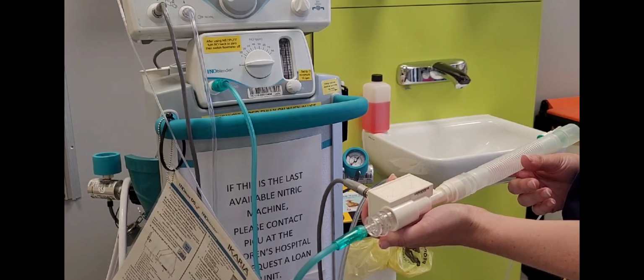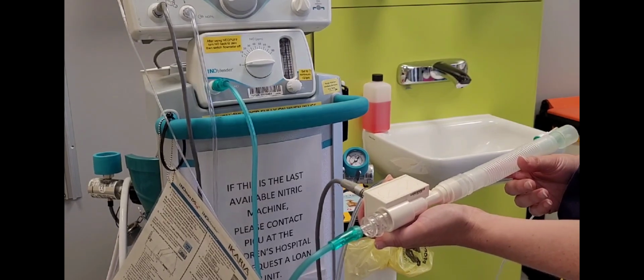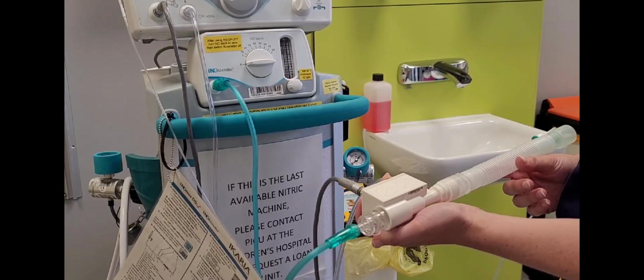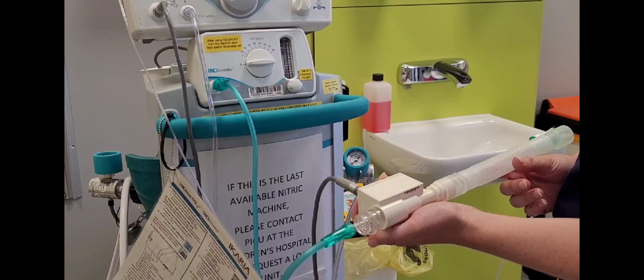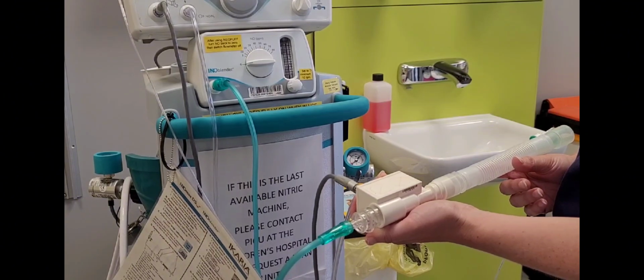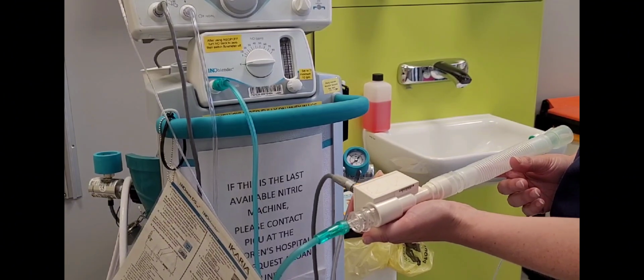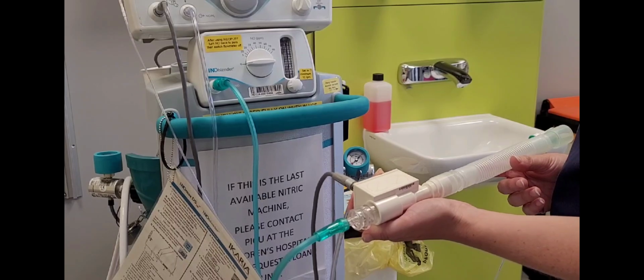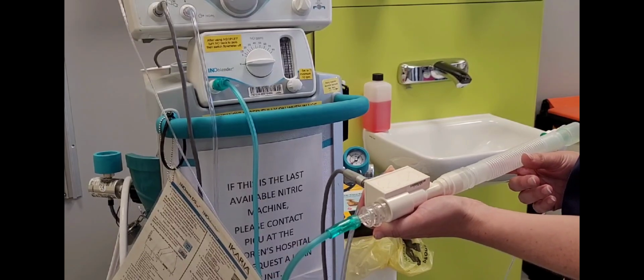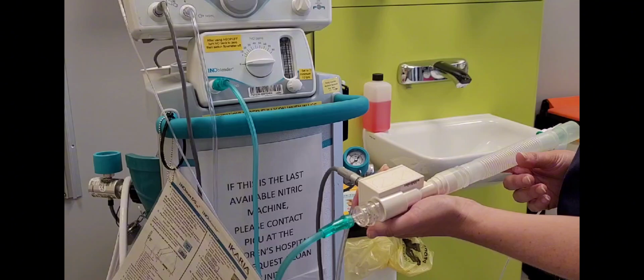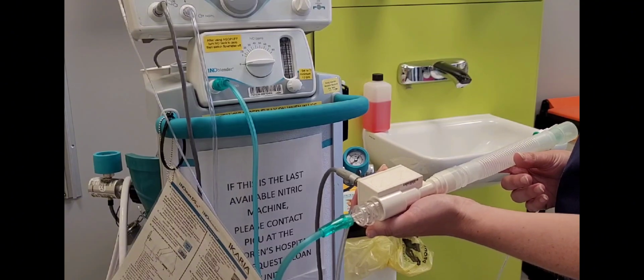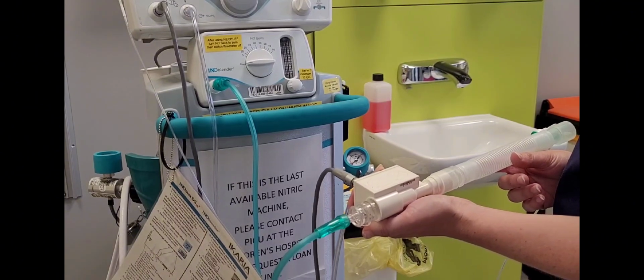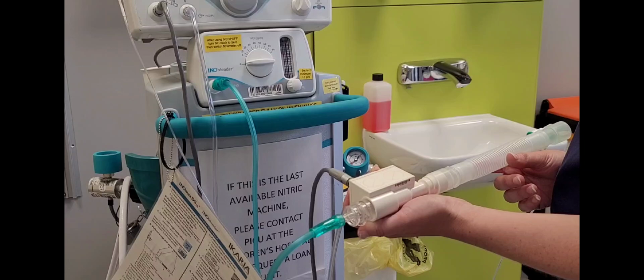This video will demonstrate the setup and checking process for the INOmax. If the machine has not been set up, you will need to plug it in. Ensure you have a grey box and an available oxygen supply. The parts you need are oxygen tubing, a clear adapter, 2 green adapters, an injector module cable, injector module, hose, patient gas sample line, and nitric injector tube and the filter.